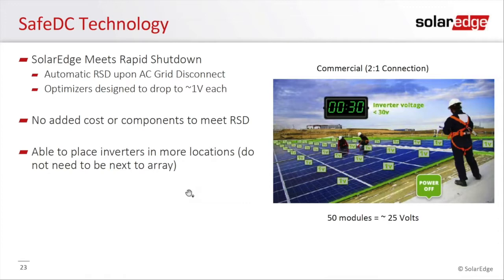The other one is more of the risk mitigation, and that's our Safe DC technology. This is really the roots of SolarEdge, how the company got started, and the use of optimizers, where the default voltage of an optimizer when you have no grid present or when the inverter shuts down, for example, in the case of a rapid shutdown, the optimizers automatically default to 1 volt. So if you had a string of 8 or 9 optimizers, you know that your default voltage would be 8 or 9 volts. And that's really how the rapid shutdown works as well, and why we're able to so easily meet rapid shutdown requirements regardless of where it is in the country and which code level you're at.